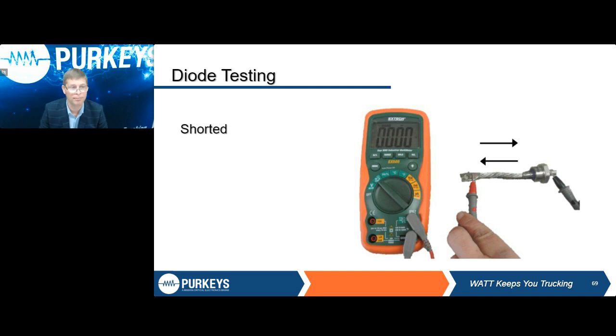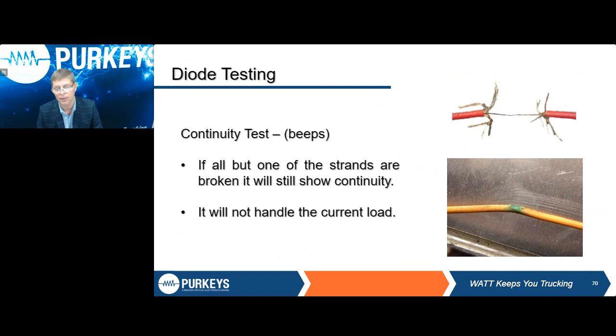Next on that knob setting or meter setting is diode testing / continuity check. A continuity check can be a wonderful function, but it can get you in a lot of trouble. If you look at the screen, the top right picture, that's a piece of 10 gauge wire that has every single strand but one broken. Will that wire show continuity? Yes, it will. Can that wire handle any current?